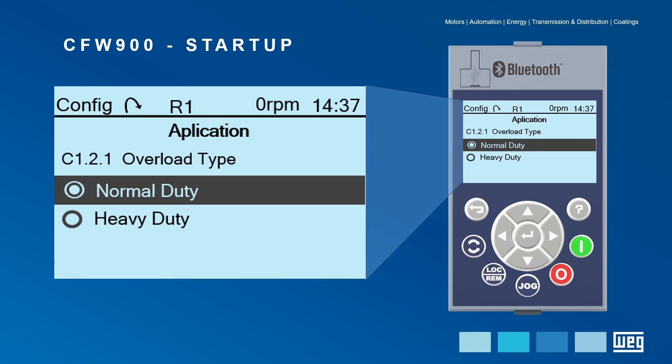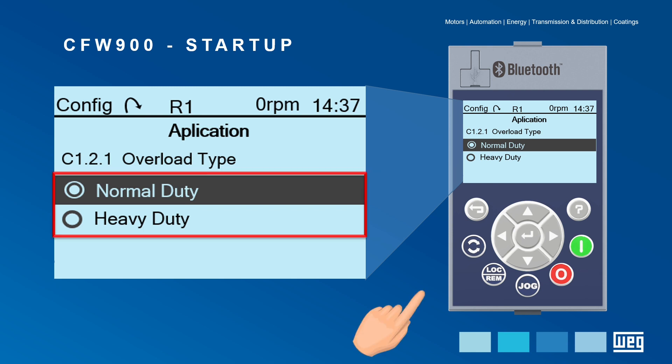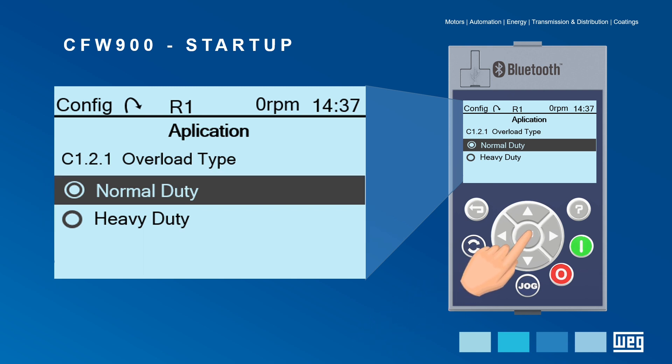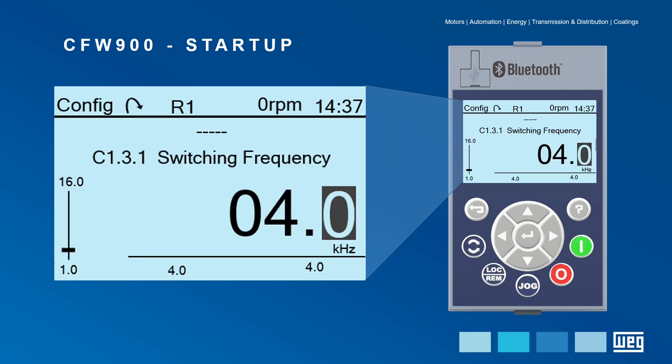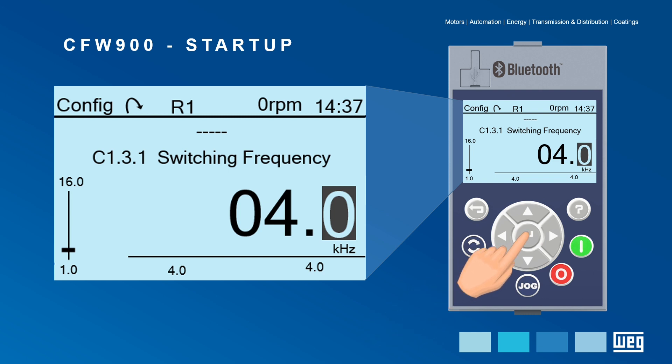Select the overload type taking into account the drive's application — choose between normal and heavy duty — and move on. The switching frequency may be kept as the default value, except in special application cases.